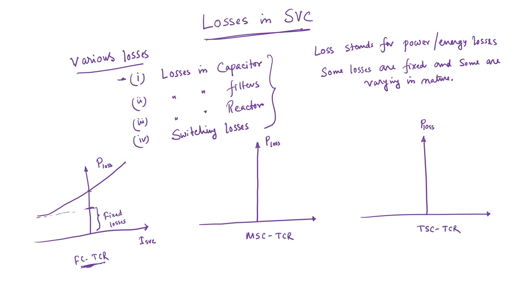In case of MSC-TCR, the loss characteristic has fixed losses as well—let's say this is the amount of fixed losses. The usual characteristic looks like this. If we turn on different discrete values of the capacitor, the losses increase accordingly.